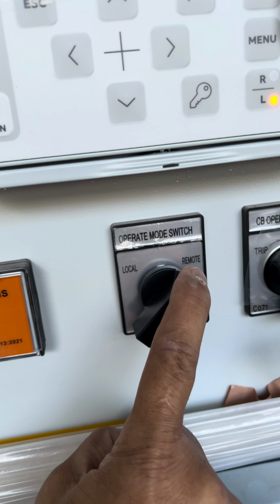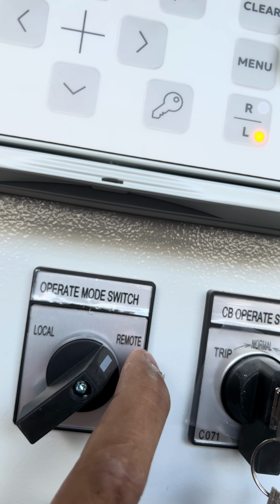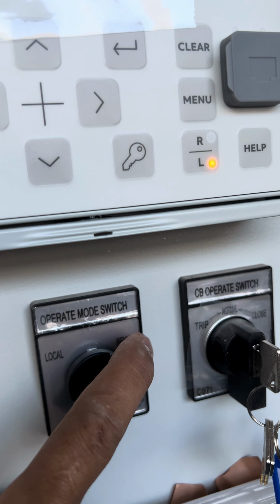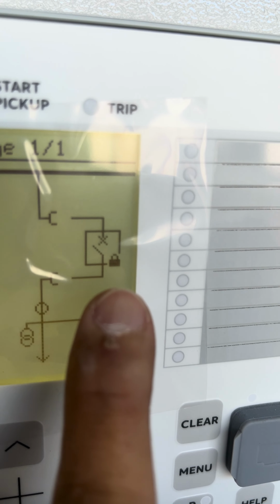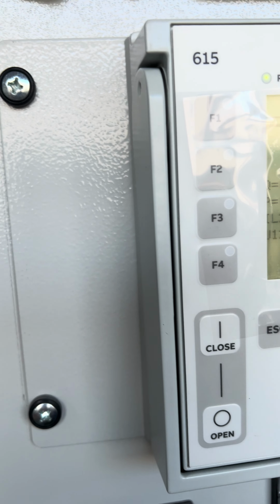If you see, guys, we are at the auto or remote mode. So when the selector switch is switched this way, this is the one that will be controlling. Okay. So let us see. Earth first, it cannot operate yet. Earth first. So for now, the earthing switch is open. Okay. Close, close. Close. Close. Let's open it, sir. Okay, right. So the earthing switch is closed and it is indicated here.